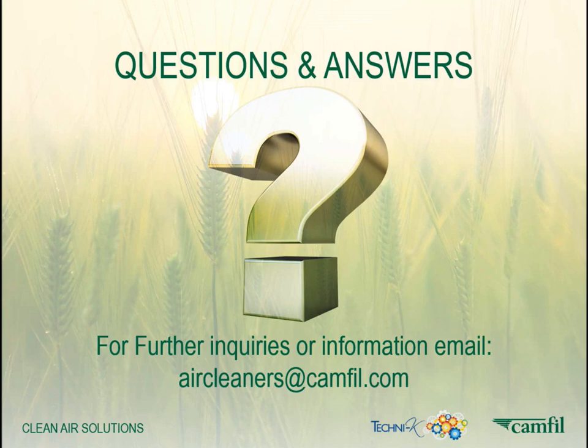Here's one about post-filtering. After filtering, what about the filtered particles? What happens there? I assume they're asking about particle shedding. That doesn't happen from non-shedding filter material, so there should not be any particle shedding from the filters. There would not be any risk of that. I think they might be asking, when the filters are working and take the particles out of the air, where do they go? Oh, they're captured within the filter media. As the air passes through the filter media, the particles are captured within the fine fibers of the filter media.